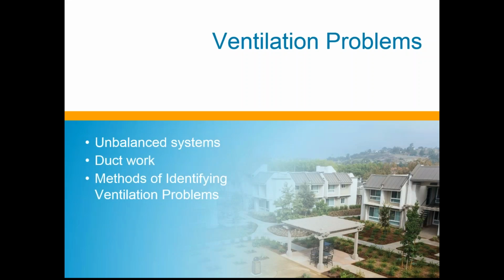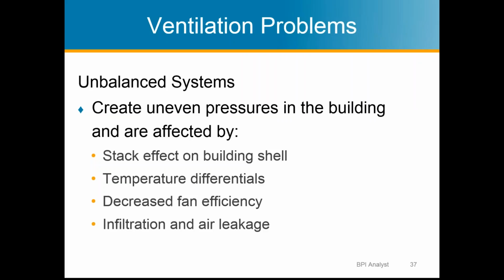All right, so ventilation problems that you'll run across. Unbalanced systems, like I mentioned before, will create uneven pressures in the building. Mainly, we don't know where the makeup air is coming from. It's always coming from somewhere. You could have a large negative pressure build up in the house, like I talked about the one house that I'd measured. But even at negative 25 pascals, that's just the pressure at which it needed to be to get enough air inside the house. So where's that air coming from? You know, around the doors, through the insulation, maybe through the attic or the crawl space, but it's leaking into the house from somewhere.